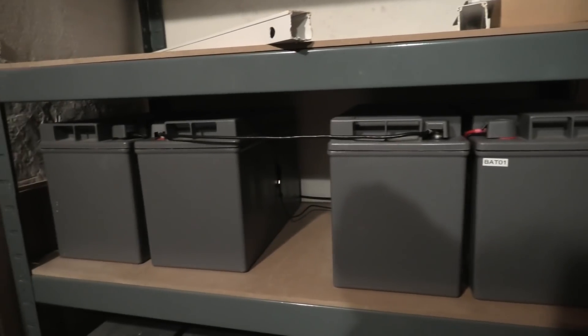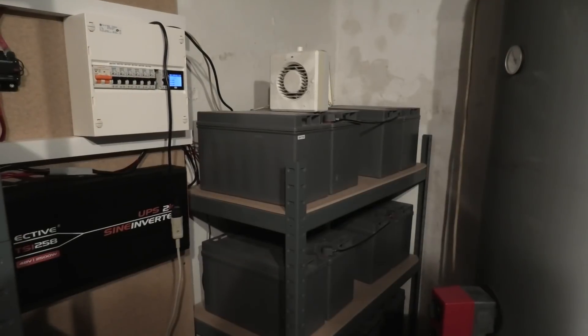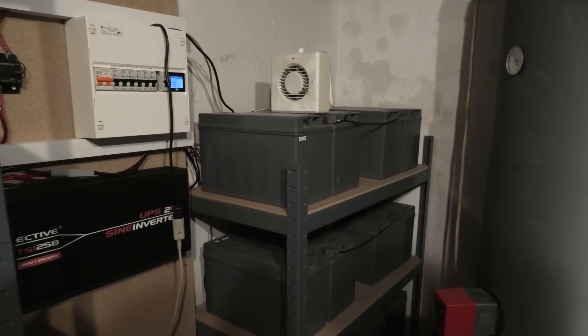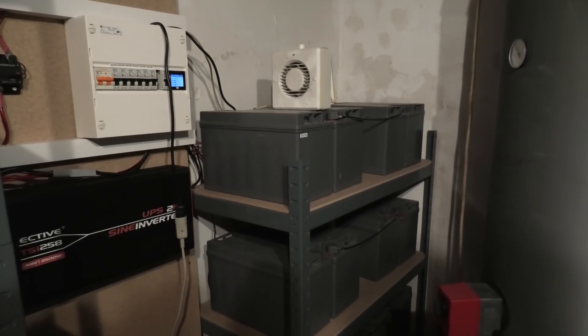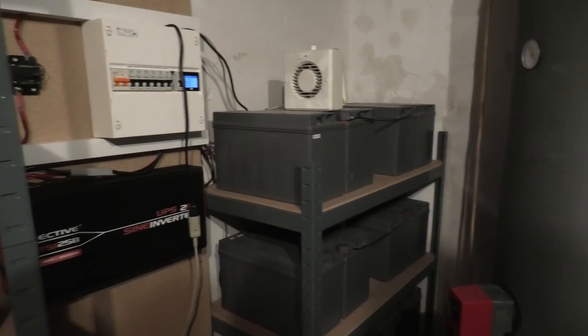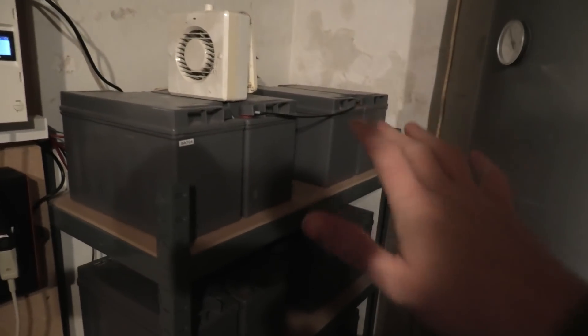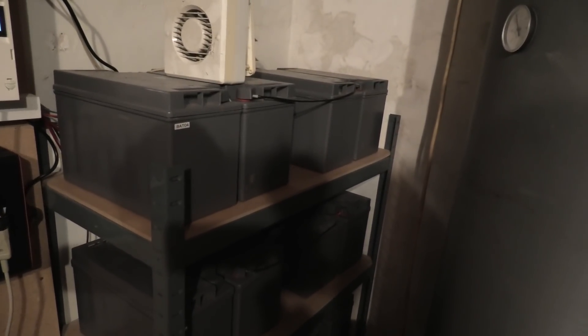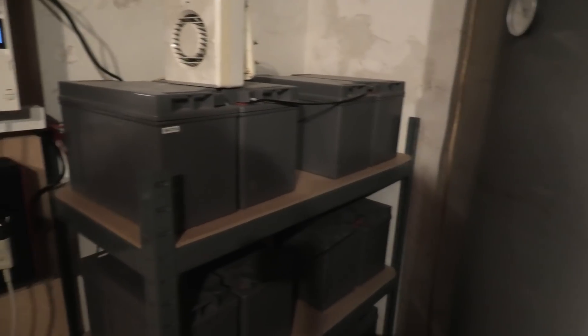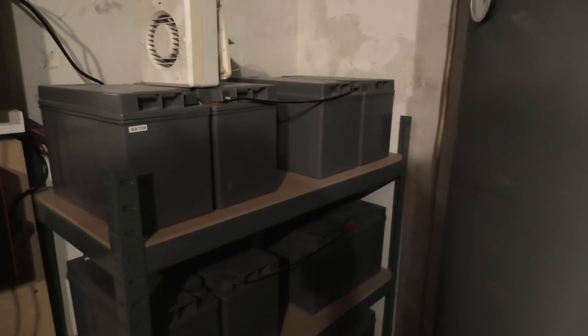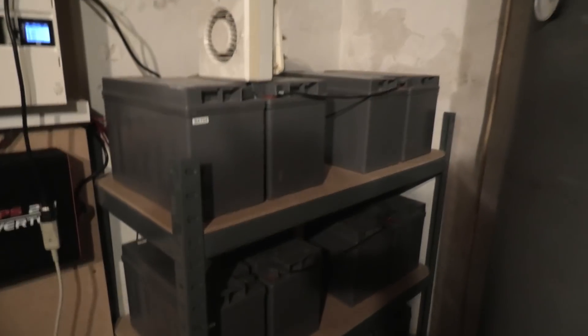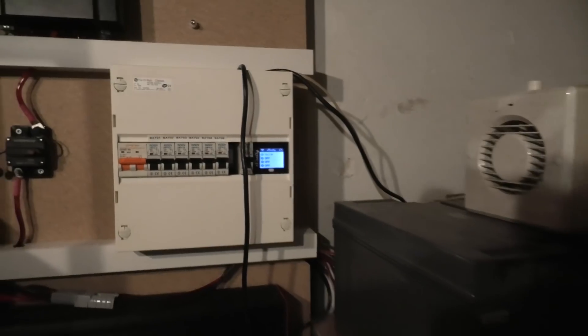These are really old batteries. They look really good here, but if they were all brand new and had all the capacity they were once delivered with, I should have 24 kilowatt hours of battery power. I do not have that. I think I might have about 8 kilowatt hours, just because you can't get all the power out of lead acid batteries and they're old and worn. They are closing up on 15 years, I guess, 12 to 15 years.